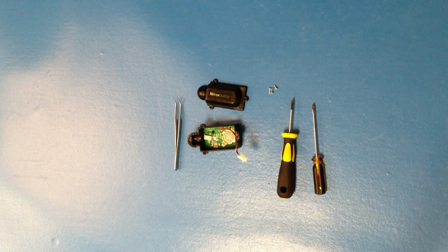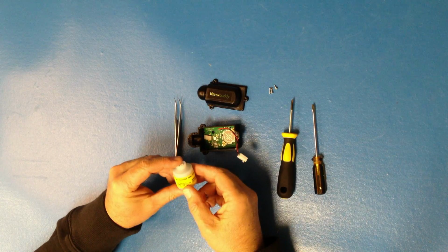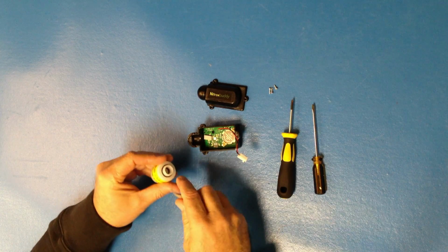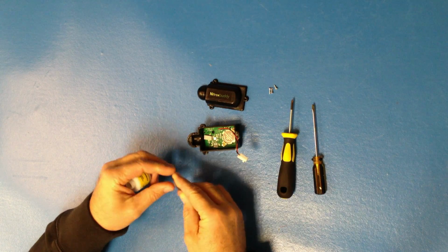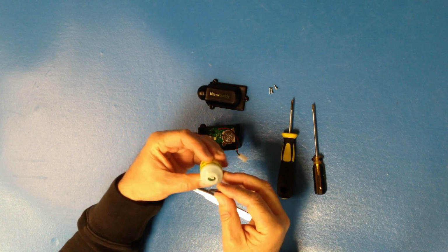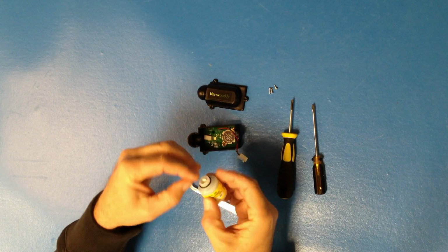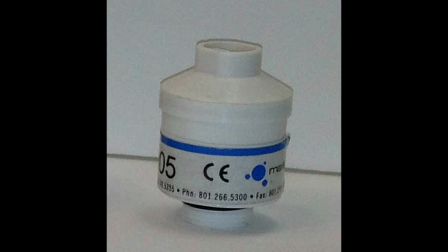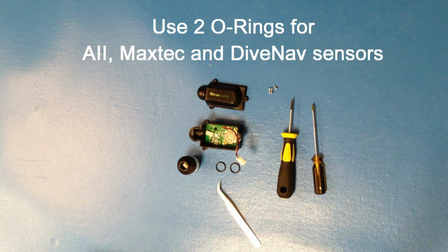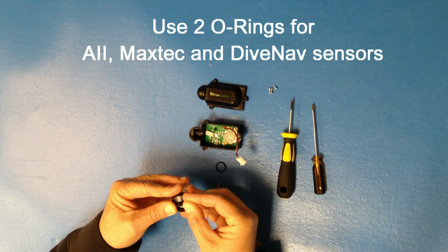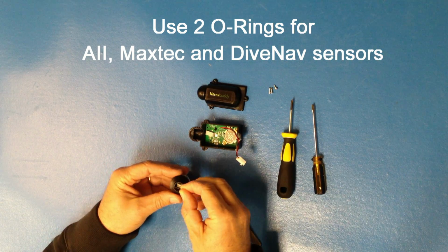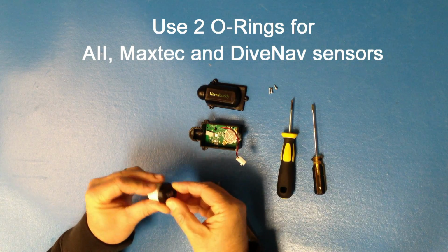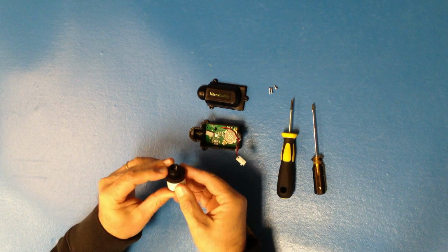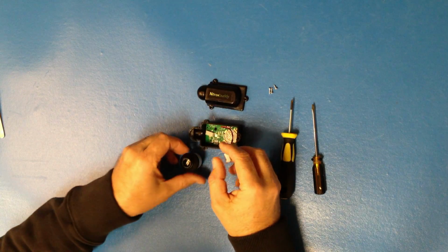Time to put in the new oxygen sensor. But first, we need to adjust the O-rings. Remove the O-ring from the front of the sensor and place it in the back. If you're using a Teledyne sensor, you're ready to go. But if you're using an Analytical Industries sensor, or a Maxtec, or a DiveNav one, you will need to add a second O-ring. Once the O-rings are in place, you can insert the female connector into the sensor.